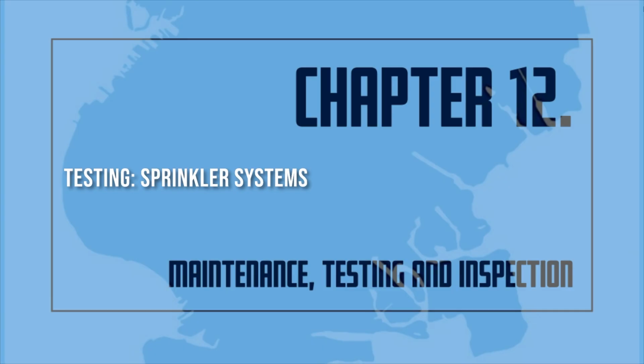Sprinklers, fast response. Sprinklers using fast response elements that have been in service for 20 years shall be tested. They shall be retested at 10-year intervals. Sprinklers from sample areas that do not pass performance standards shall be replaced. Old sprinklers. Where sprinklers have been in service for 50 years, they shall be replaced, or representative samples from one or more sample areas shall be tested. Sprinklers from sample areas that do not pass performance tests shall be replaced. Test procedures shall be repeated at 10-year intervals. All sprinkler heads manufactured prior to 1920 shall be replaced.